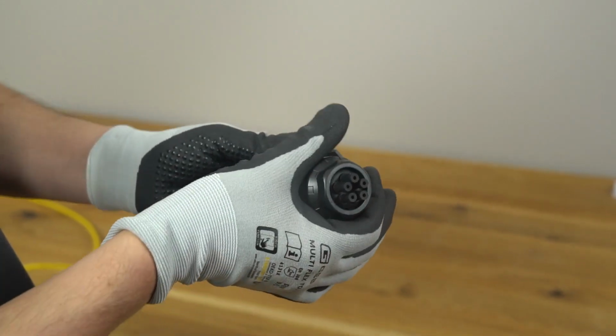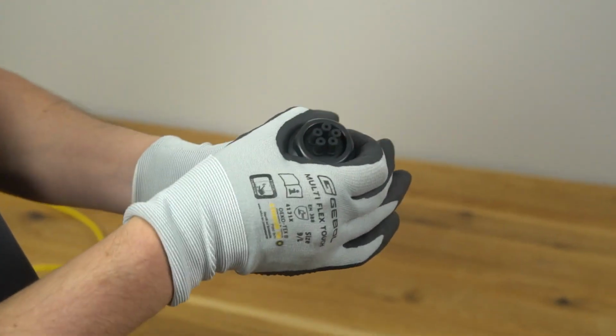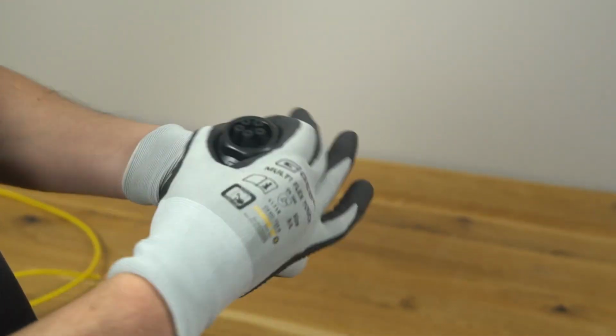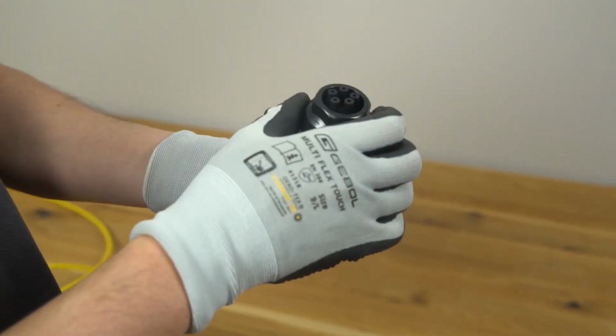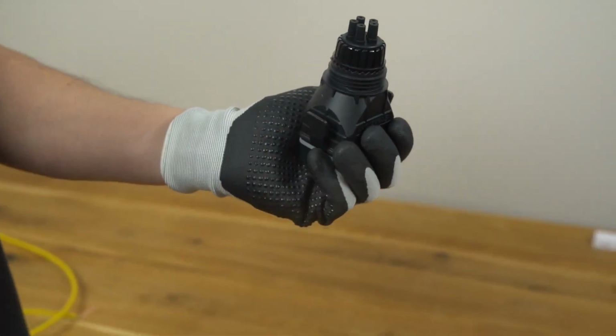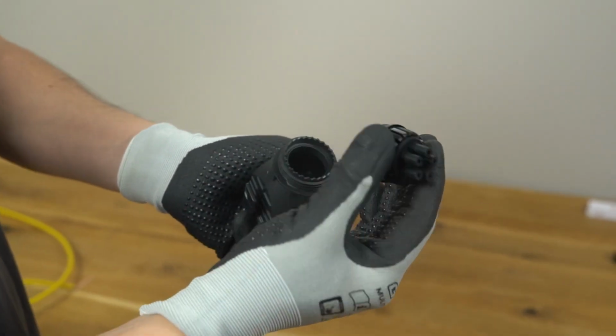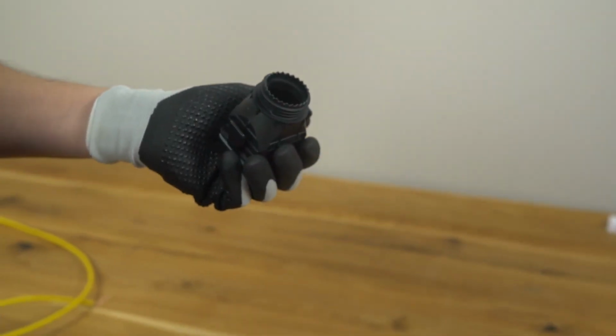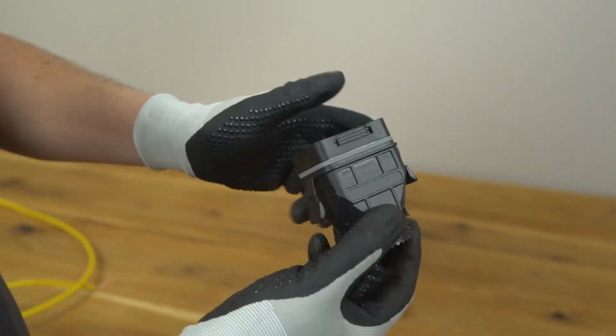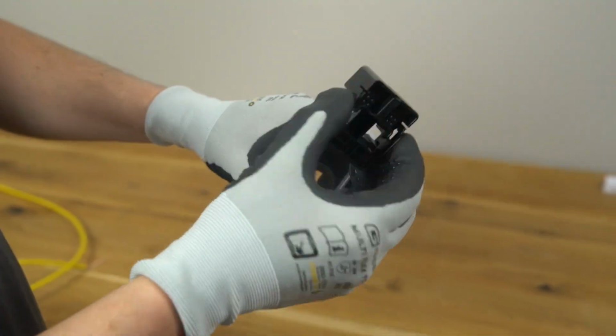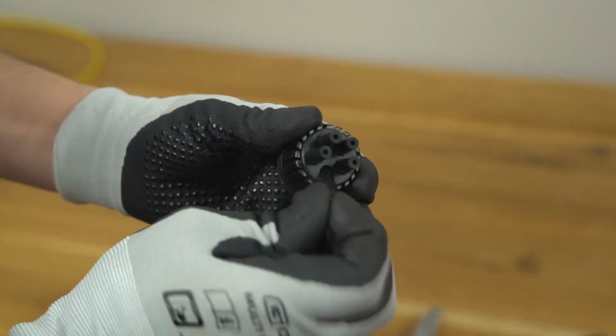Now let's continue with the communication terminal named COM2. The COM2 terminal is used for establishing RS485 communication with devices such as the energy meter, the battery or the heat pump. Unscrew the swivel nut from the connector and take out the terminal block. Remove the seal and lead the cable through the cable gland.